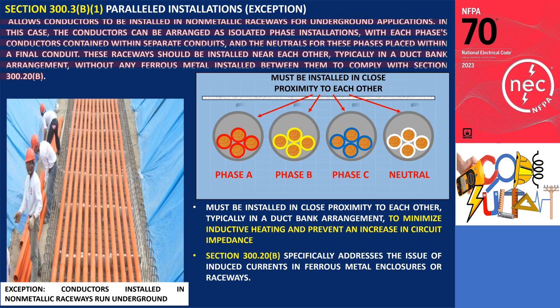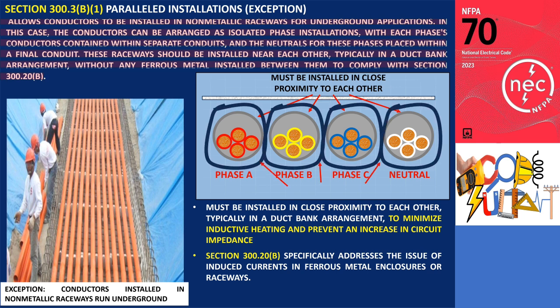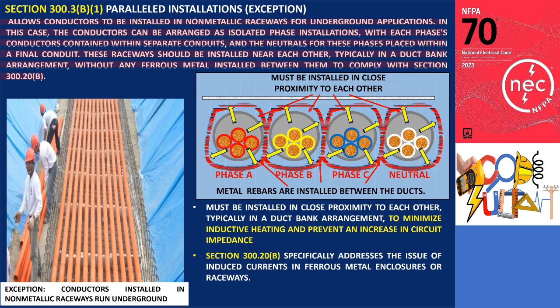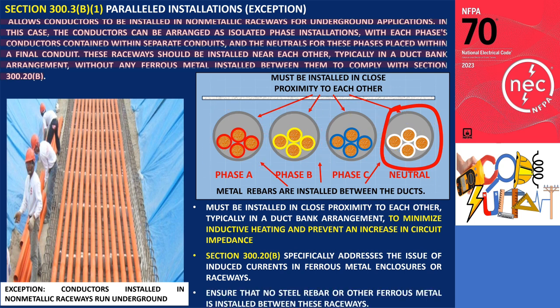When an alternating current conductor passes through ferrous metal, it generates an induced current that causes the surrounding metal to heat up. To avoid inductive heating, it is necessary to ensure that no metal is installed between the ducts.